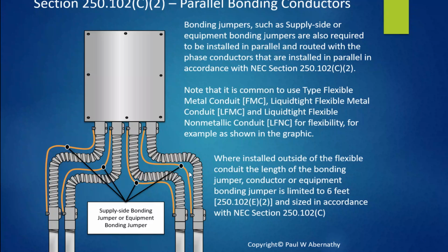So you have to run in parallel the supply side bonding jumper, or if it's on the load side of the service disconnection means, then this would be what's called an equipment bonding jumper. Just wanted to point out it's done the same way, whether or not it's on the supply side or on the actual load side. Now, the only caveat to that, and what I want to do is I want to bring up the code. So I just wanted to show you what I call my FMC octopus here.